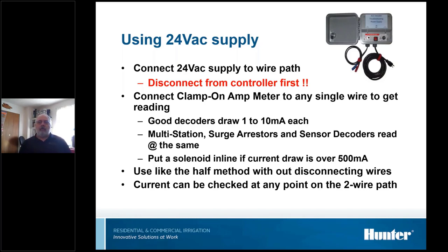Then I'm going to go halfway out, or whatever makes sense. All I've got to do is get in there, get on the wire and read it. So you don't want to read the individual decoders until you get right down to the final end, so you're narrowing down on the actual one. You just grab one of the heavy wires, either red or blue, and get a reading. If it's high, your problem's further out. If it's low, then your problem's between you and the controller. So what you're actually doing is looking for that break, the point where the current draw number goes down dramatically. And once you've found that, then you just back up to your problem.